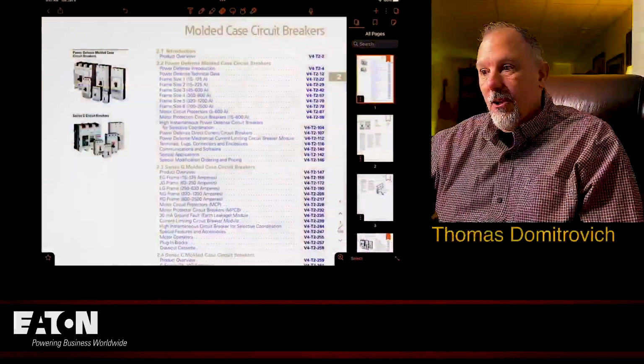So these trip units, these brains, will tell you the functionality of the circuit breaker. This device will open everything up here. The mechanism will open when that brain tells it to open. So what we are going to do is go to the catalog to figure out what is the smallest overcurrent protective device that we can use and leverage an arc reduction maintenance switch. So let's take a look at our catalog.